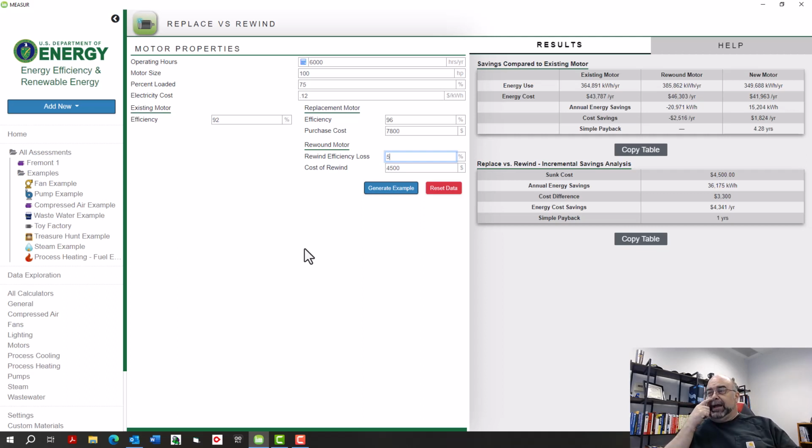But anyways, back in the day, BC Hydro in Canada, Ontario Hydro, and Hydro-Quebec all did a series of studies. Two were blind studies, and the Hydro-Quebec study involved an actual rewind process, both how you're supposed to do it and ways you shouldn't do it. I got to be on the advisory group for that, 1993. So we know that 5%, if somebody does a really crappy rewind or repair, that's what we're going to get.